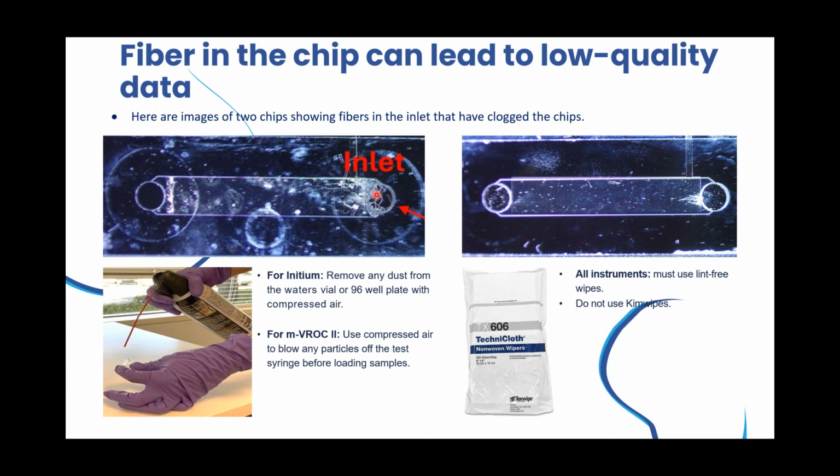We do not use Kimwipes. These should not be used with these microfluidic devices. For our Initium instruments, we recommend you remove any dust from the vials or the 96-well plate with this compressed air. For the m-VROC II, you can use this air to blow out any particles off the test syringe before loading your sample.